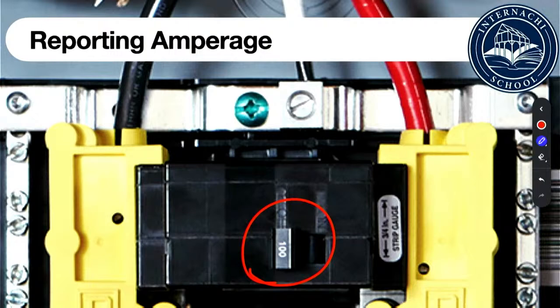But I got to share, I'm a big advocate, I want our guys to know more. If this is 100 amps, but I'm feeding it with a 10 gauge wire, that 10 gauge wire is only good for 30 amps. I should be able to recognize that and inform my client that even though this says 100 amps, it's really only a 30 amp system, but I'm going to allow 100 amps to go through it, which makes it a dangerous situation. Again, the more we know, the more we're worth, and people rely on us when they buy their homes.